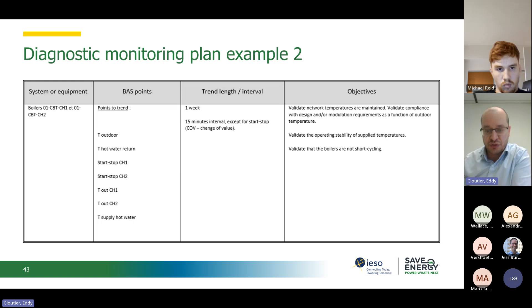Okay, let me go back to the presentation. So in this case, we already saw the list of points. You can see that we want to record data for at least a week at 15 minutes interval. And in that case, the objective would have been to validate network temperature modulation versus outdoor temperature. So we want to check if the outdoor reset is still valid. We also want to validate the operating stability of the 2 boilers and see if they are not short cycling, which, as you might know, strongly impacts boiler efficiency.